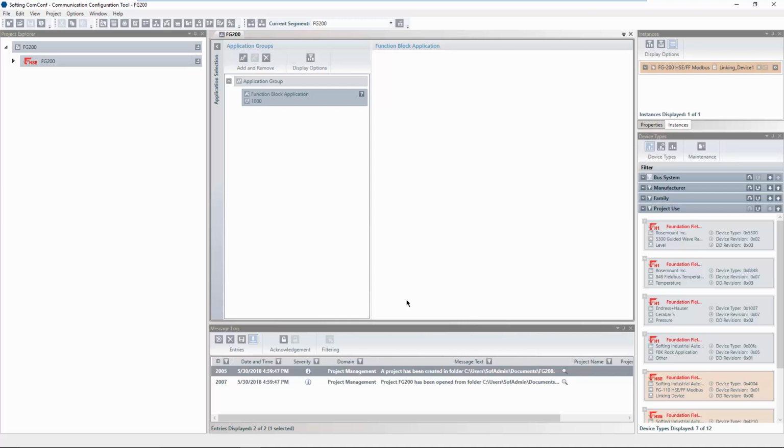When a project is created, additionally a network access profile is created automatically. This network access profile defines how the PC shall access the network you want to configure. If your PC possesses more than one Ethernet access, you must check if the correct Ethernet access has been used for the created network access profile.